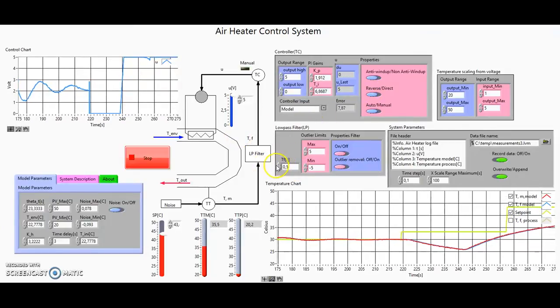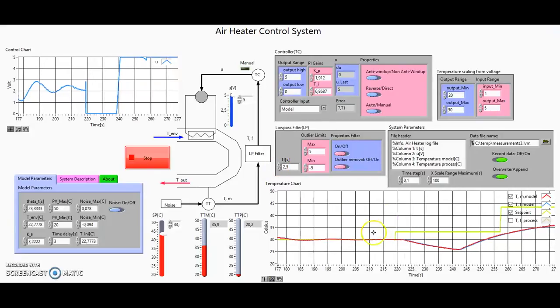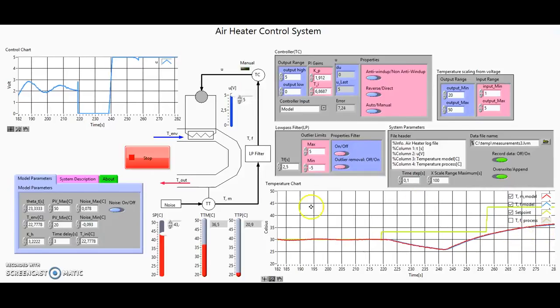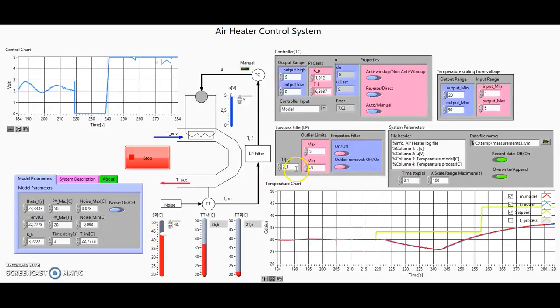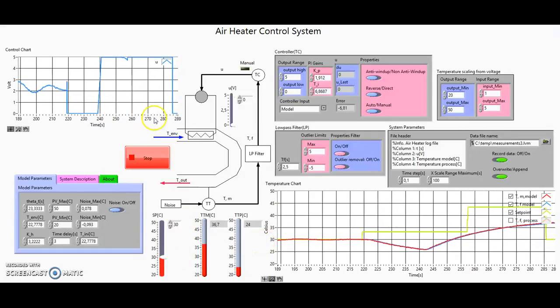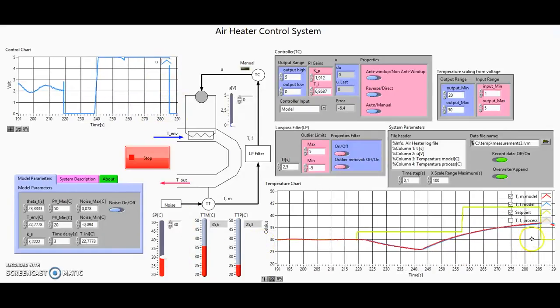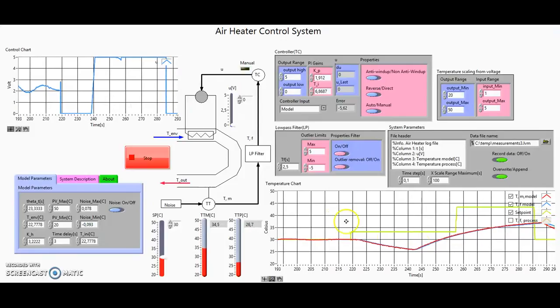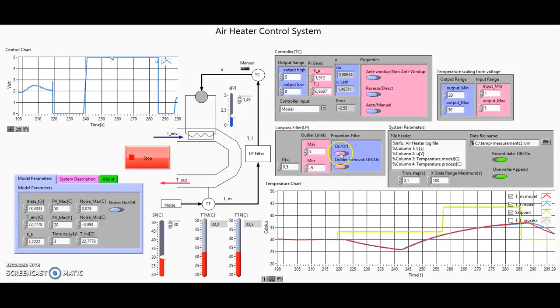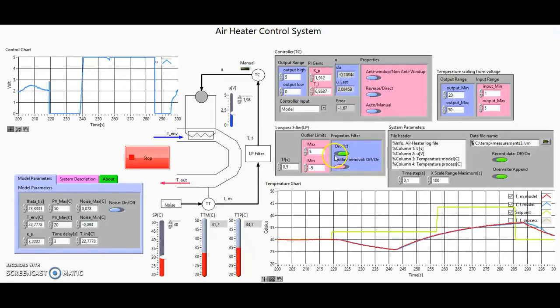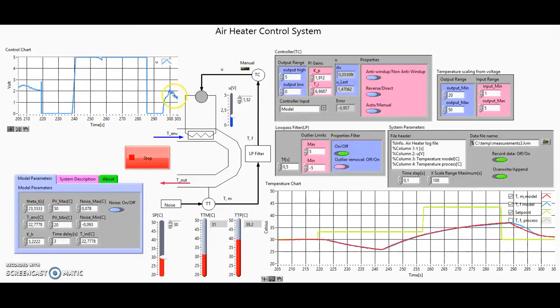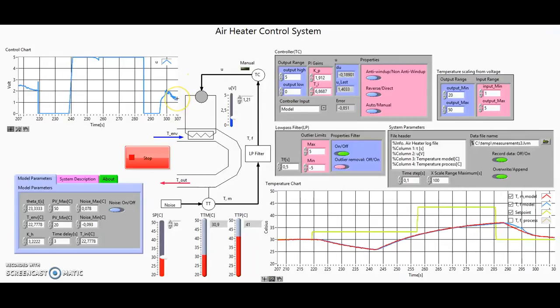Here we have the filter. A high filter constant means a more aggressive filter. We set the filter constant to 2.5, and we can see a really large phase shift. The filter can also be turned on and off — if you turn it off, you see a very large increase in the propagation of noise through to the control signal. Turning it on again, the noise decreases.